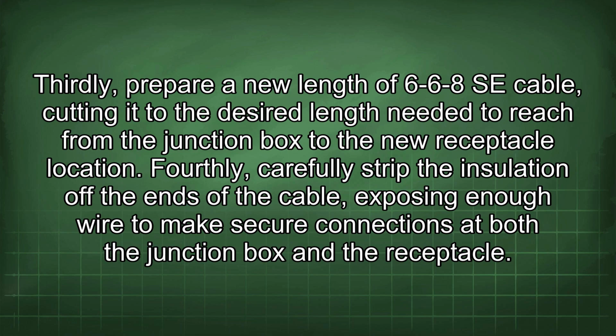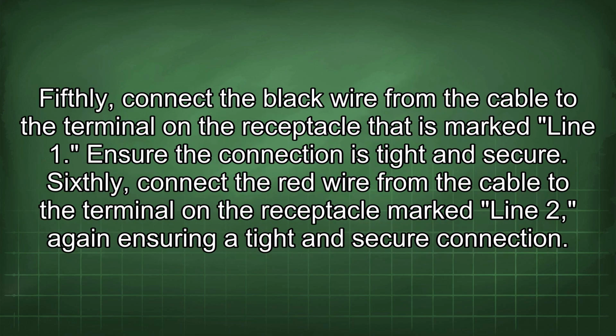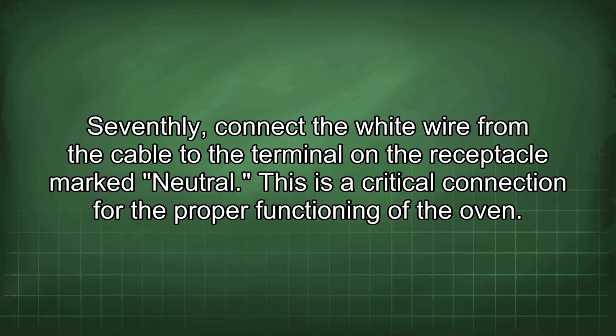Fourthly, carefully strip the insulation off the ends of the cable, exposing enough wire to make secure connections at both the junction box and the receptacle. Fifthly, connect the black wire from the cable to the terminal on the receptacle that is marked line 1. Ensure the connection is tight and secure. Sixthly, connect the red wire from the cable to the terminal on the receptacle marked line 2, again ensuring a tight and secure connection. Seventhly, connect the white wire from the cable to the terminal on the receptacle marked neutral.